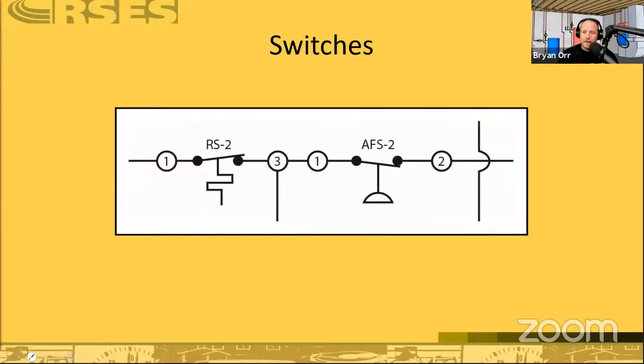In this illustration we've got a pair of safety switches. RS2 is a temperature safety, we've talked about that before. AFS2 is a pressure switch. This is a normally closed, single pole single throw, normally closed, open-on-fall, pressure-activated switch.